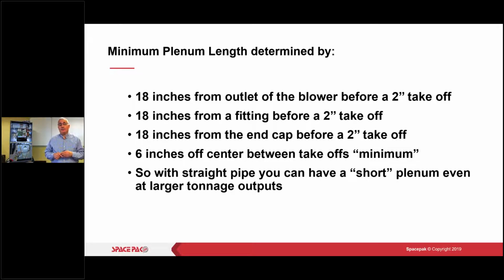I've been on jobs where here's my end cap and there's a drop right there. No bueno. It's not good. Got to be 18 inches away. And then here's the biggest one, 6 inches on center from your takeoffs. Okay, so here I got a 2-inch takeoff, here I got a 2-inch takeoff, 6 inches on center. That's my minimum. And we still see jobs where they're almost on top of each other. Okay, not good, guys, not good.